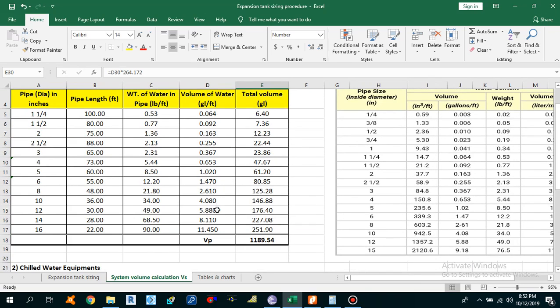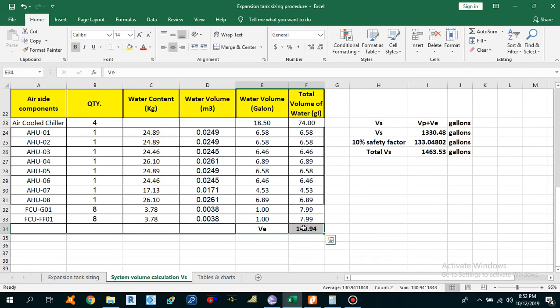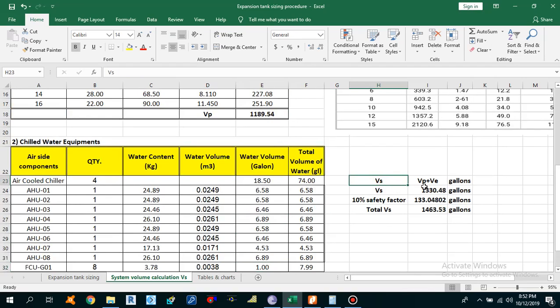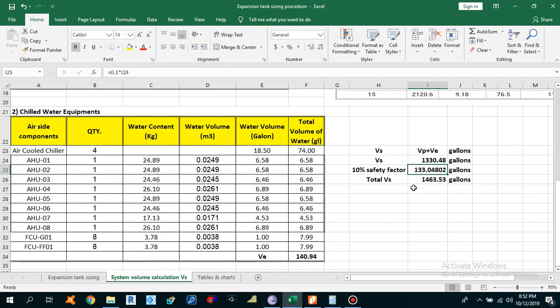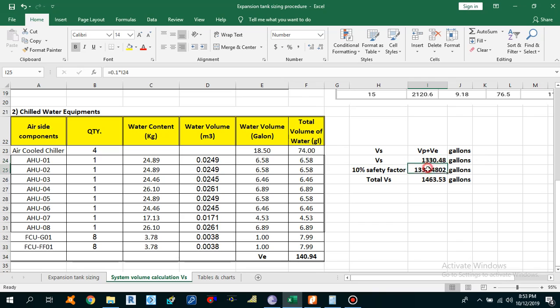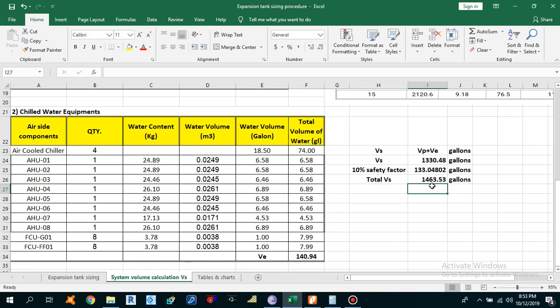Total system volume = pipe volume + equipment volume = 1,189.54 + 140.94 = 1,330 gallons. Applying a 10% safety factor: 10% of 1,330 = 133 gallons. Therefore, the total system volume Vs = 1,330 + 133 = 1,463.53 gallons.